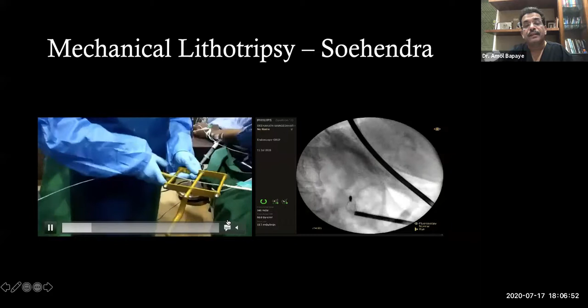And then once the stone is grasped in the metal sheath, we attach the metal sheath to this cranking device, this handle, and ensure that the basket is tightly wound around the cranking device. And then gently, click by click, slowly we have to ensure that the pressure is built up on the stone. If we try to do this very quickly, then the chances are that the basket wires will break, but the stone will not break. So slowly and steadily, you increase the tension so that the basket wires embed and cut through the stone, rather than the basket wires getting fractured themselves. So that is very important.